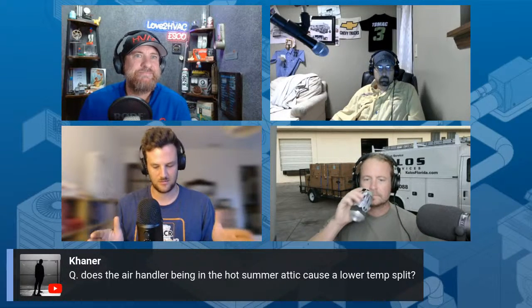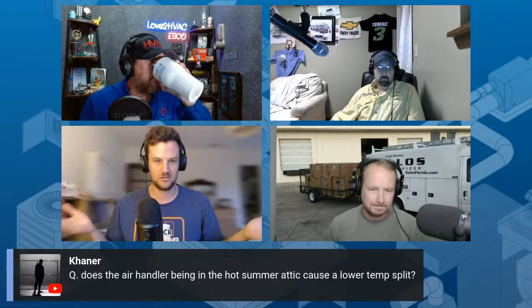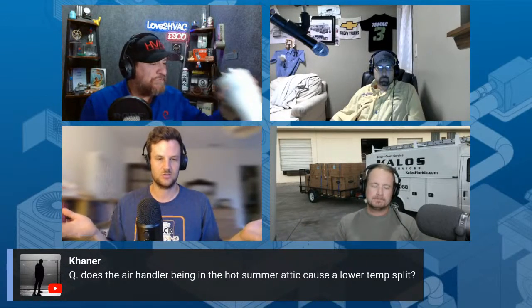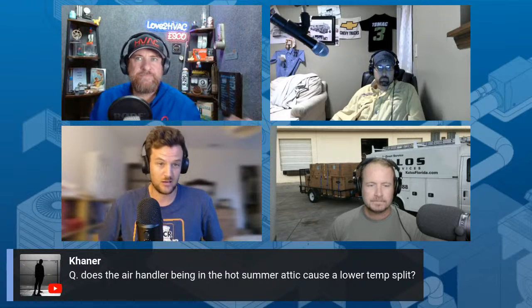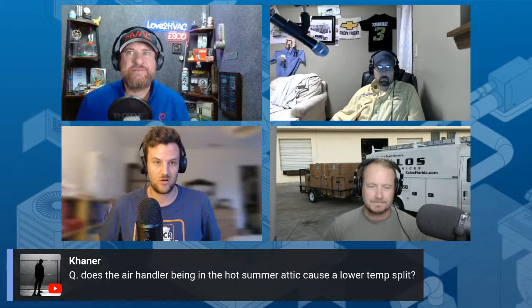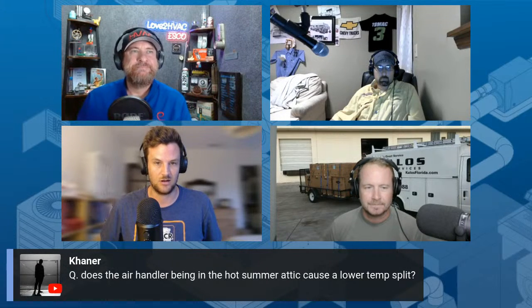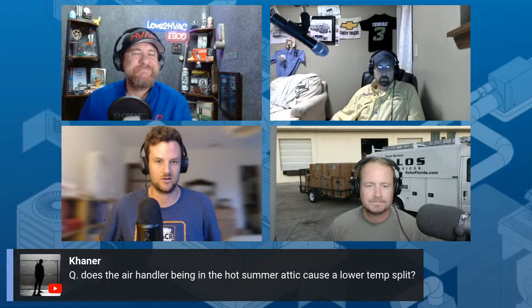Yeah, I think what you said is a good test. Sometimes I'll check that - I'll check the temp, what I call a delivered capacity or delivered temperature split. Then you go up in the attic and check it, and you're like, okay, the equipment's fine, there's nothing wrong with the box that's making the cold air. It's the distribution system getting the cold air to the house that's the problem. So it can be a really great test.